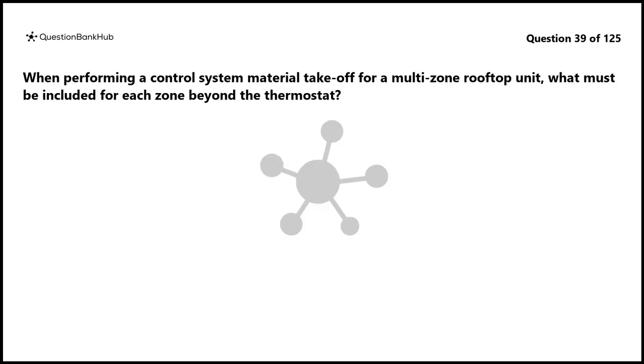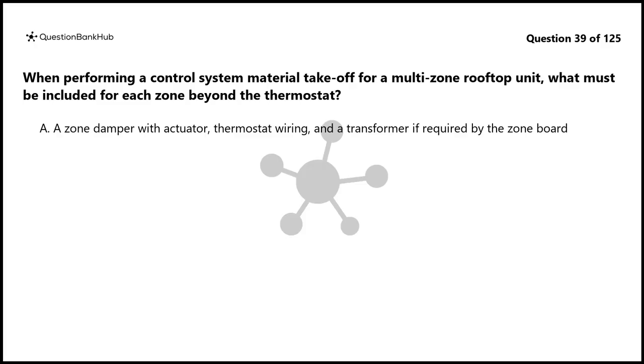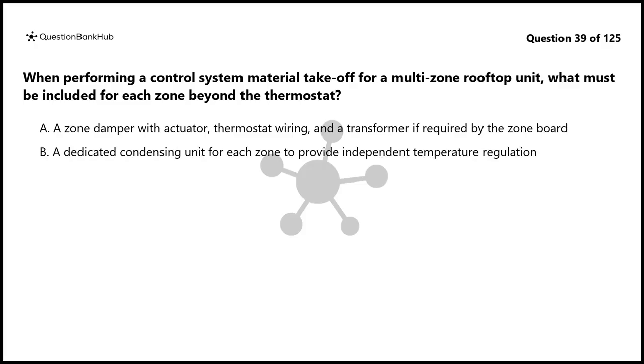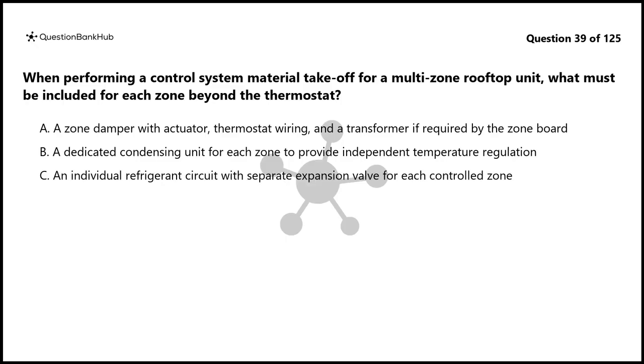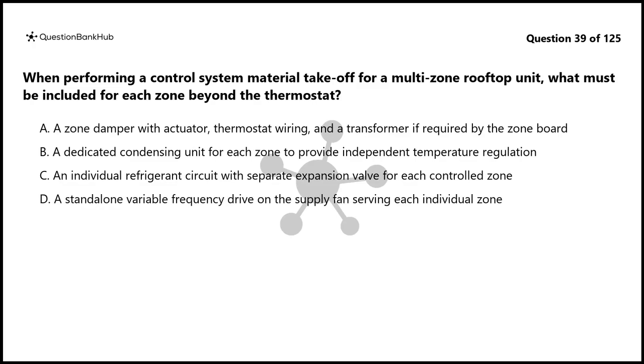Question 39. When performing a control system material takeoff for a multi-zone rooftop unit, what must be included for each zone beyond the thermostat? A. A zone damper with actuator, thermostat wiring, and a transformer if required by the zone board. B. A dedicated condensing unit for each zone to provide independent temperature regulation. C. An individual refrigerant circuit with separate expansion valve for each controlled zone. D. A standalone variable frequency drive on the supply fan serving each individual zone.